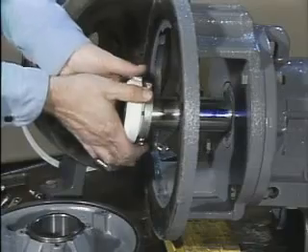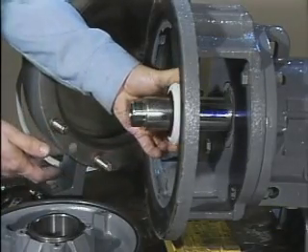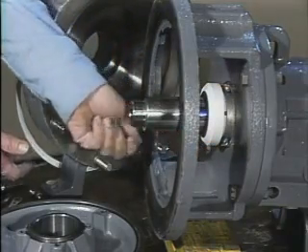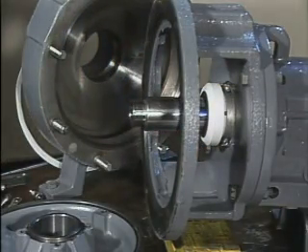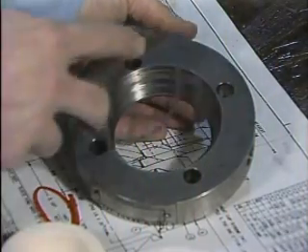Now let's look at a demonstration of how a typical outside seal is installed, after the necessary preparations and installation measurements have been done. First, the rotating element is placed on the shaft and slid back against the bearing housing. In our example, no shaft sleeve is used, so the seal components are mounted directly on the pump shaft. Then the stationary element is prepared for installation.